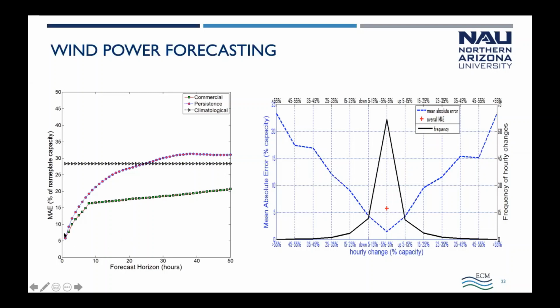The plot on the left shows the mean absolute error of wind power forecasts. Focusing on the bottom line, this is a professional forecast from a wind power forecasting firm. Inside 10 hours of when the wind's going to happen, that error will be around 5%, going up to about 10-15% depending on the forecast area. As you forecast out over 40 or 50 hours, that forecast error goes up to about 20% mean absolute error. So you can forecast the wind with some accuracy.